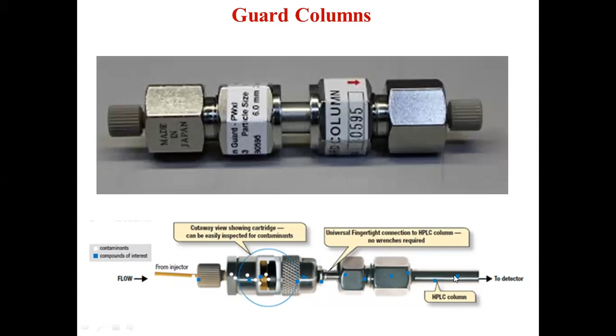Then the solutes, after getting separated in the analytical column, will be moving towards the chromatographic detector. So you can see here the performance efficiency of the HPLC for the separation of 8 compounds like paraxylene, anisole, benzyl acetate to diethyl phthalate. So high speed isocratic separation has been done by means of a 4 centimeter column of inside diameter 0.4 centimeter, and the packing material is 3 micrometer particle size Perisorb, which was spherical in shape. 4.1% ethyl acetate in hexane was used as a mobile phase. Hexane is non-polar, so a non-polar mobile phase and a polar stationary phase is used here. By using this, we can separate 8 compounds within 15 seconds, you can see 15 seconds.